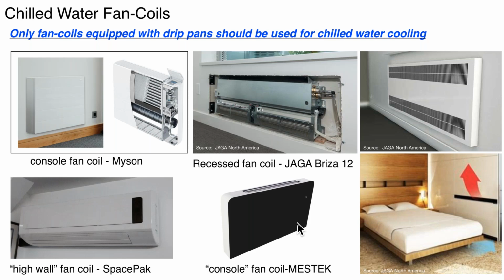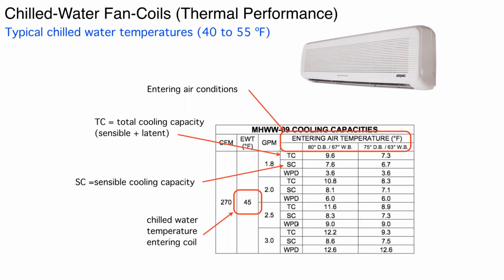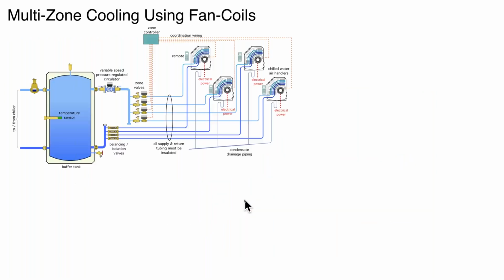And again, I stress, you definitely want to make sure the unit is supplied with a condensate collection pan, and if so, it would have a drain connection. Similar rating data to what we just talked about: total and sensible cooling capacity, different entering air conditions. In this case, it shows 45-degree entering water temperature. Typically, you'll find tables for other entering water temperatures or correction factors so that you can match the cooling capacity reasonably close to what your cooling load calculation is.